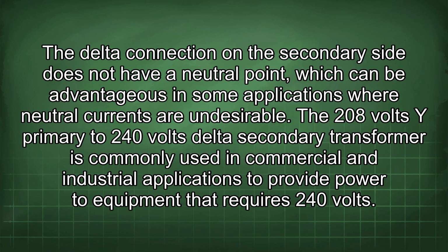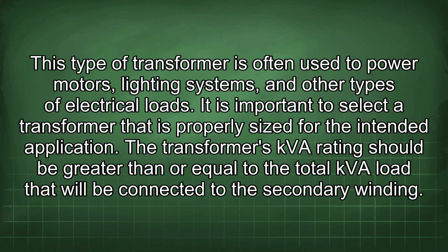The 208 volts Y primary to 240 volts delta secondary transformer is commonly used in commercial and industrial applications to provide power to equipment that requires 240 volts. This type of transformer is often used to power motors, lighting systems, and other types of electrical loads. It is important to select a transformer that is properly sized for the intended application.